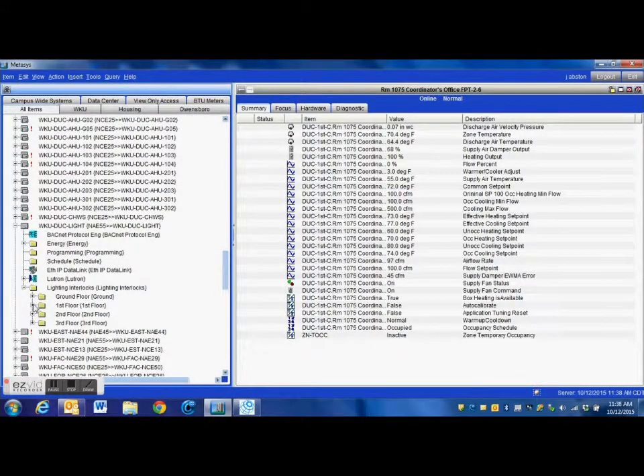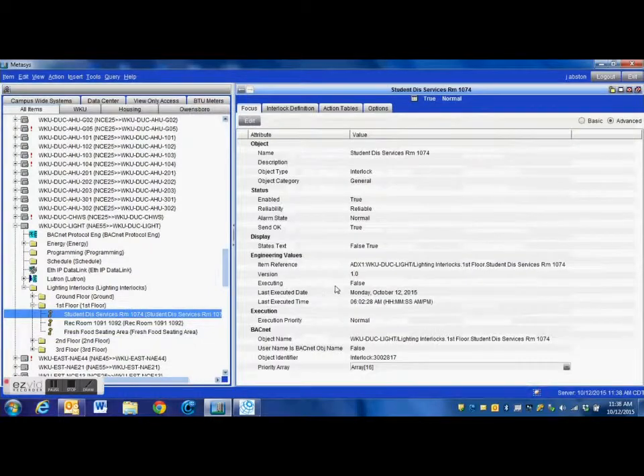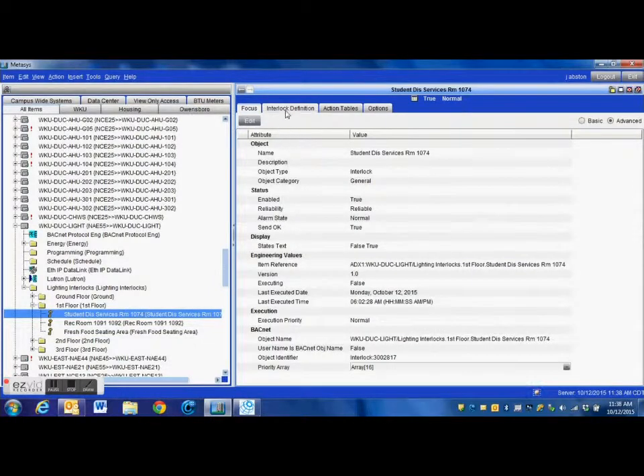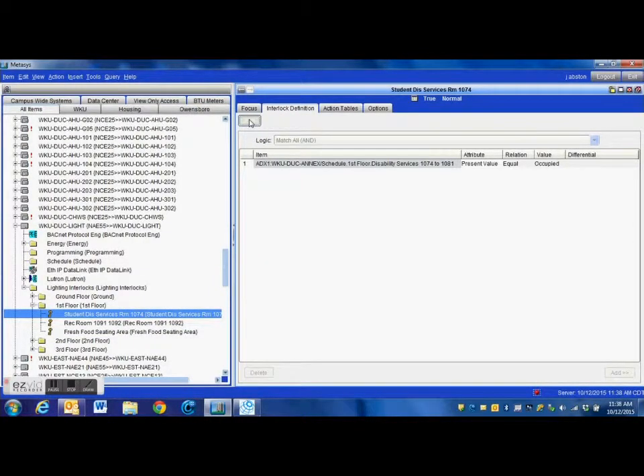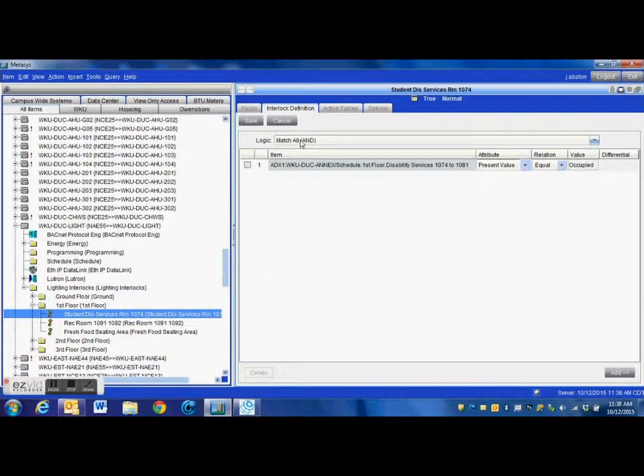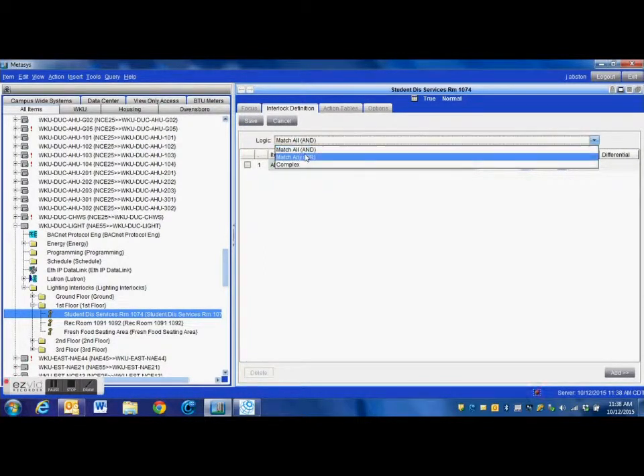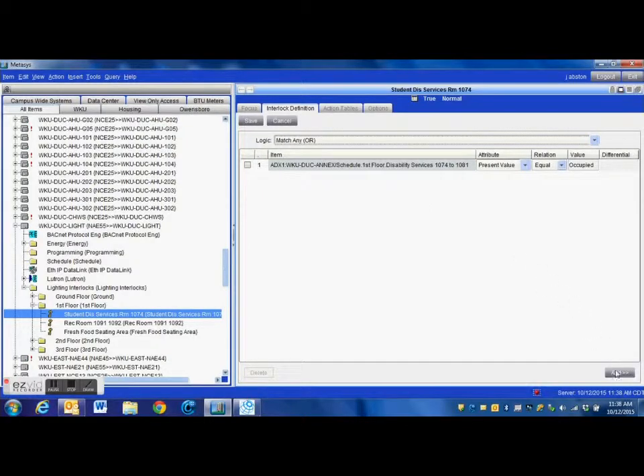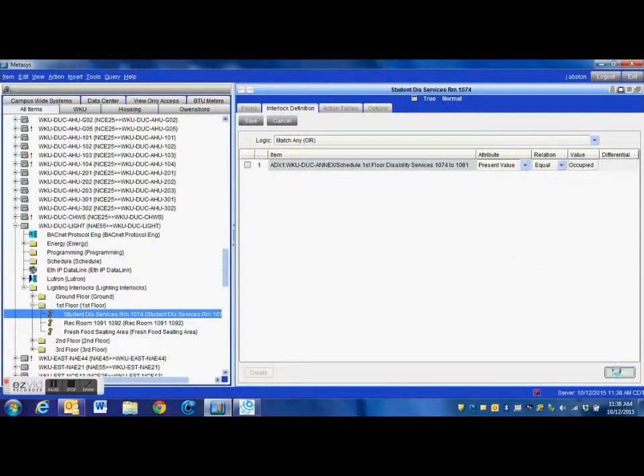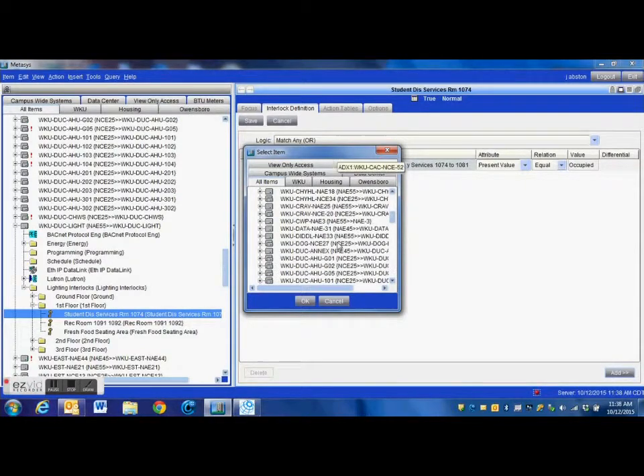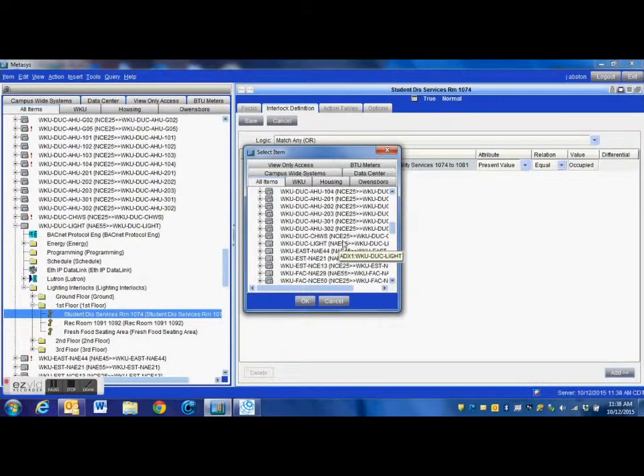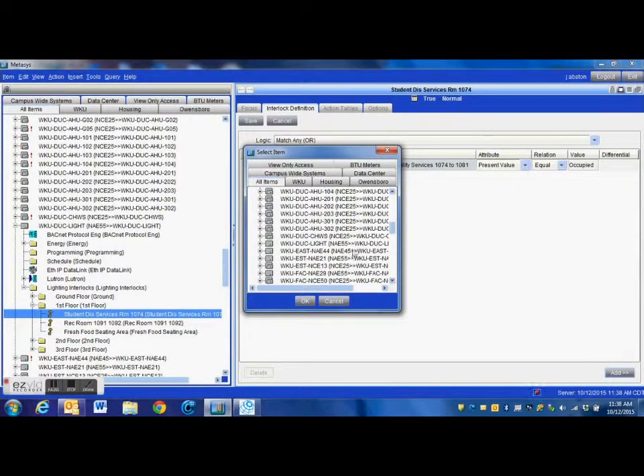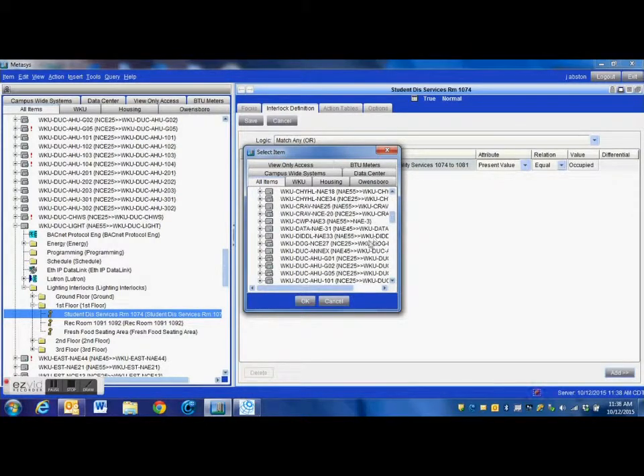Now I'm going to go down to an interlock that we already have set up where we tied the lighting schedule to zone occupancy. What I'm going to do here is simply add that point to our interlock. I want to change this to an OR type system because I want either one of these two blocks to be able to turn those lights on, whether it's the schedule or the occupancy override.